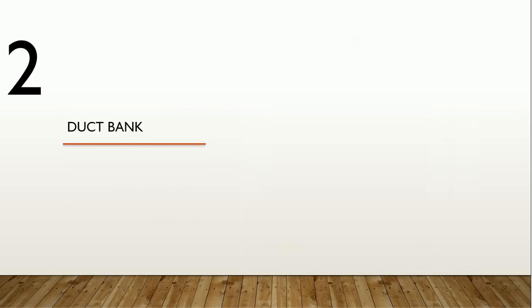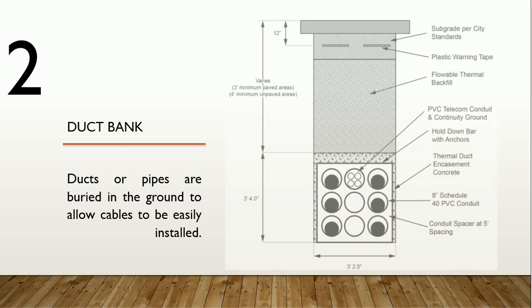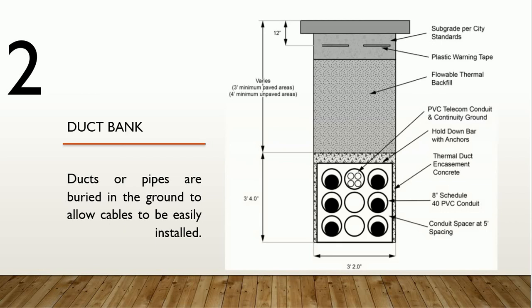The second type is duct bank. Ducts or pipes are buried in the ground to allow cables to be easily installed, which means that the pipes are encased with concrete and then the cable will be pulled inside these ducts.